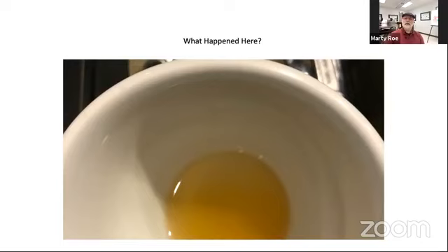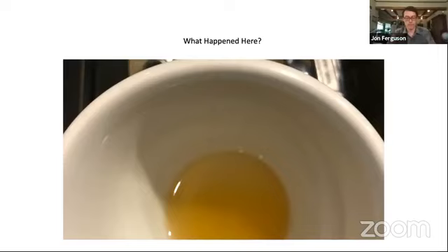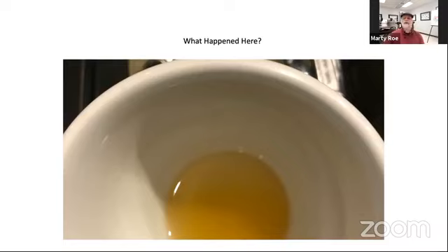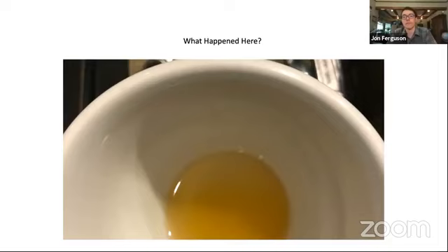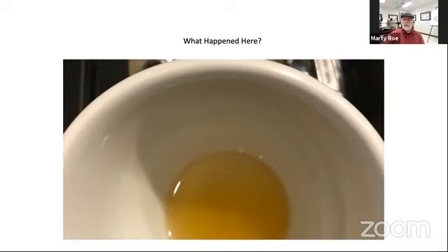So that's one possibility. The other is that over a long period, six months or more, if you're using this steam boiler and never taking anything out of it other than steam, the minerals that naturally come in each time you refill the boiler get trapped in there. So it could just be a natural elevation of minerals - we call that TDS, total dissolved solids - a natural rise from a boiler that hasn't been maintained by draining periodically.